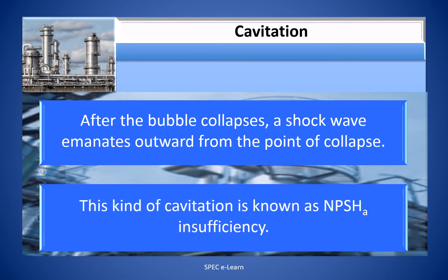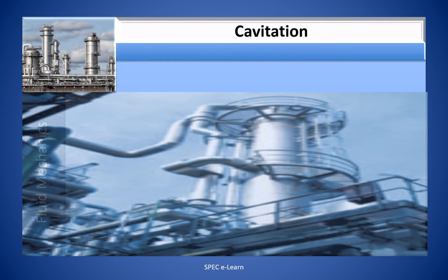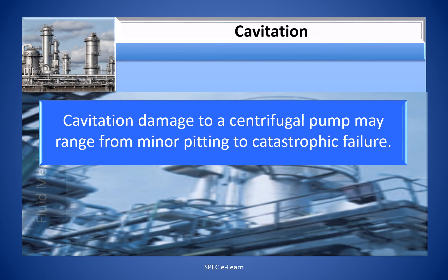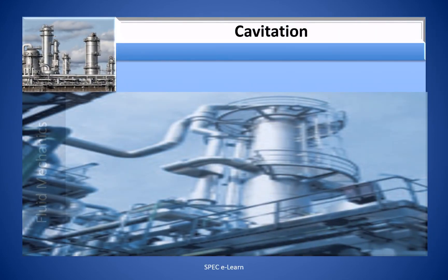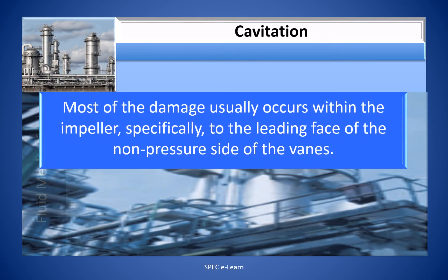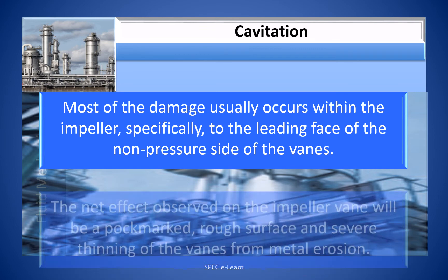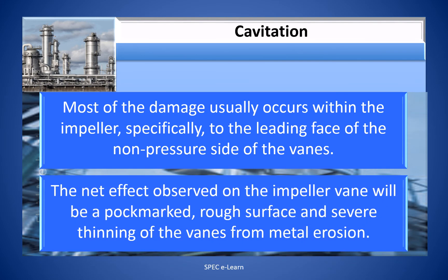Cavitation damage to a centrifugal pump may range from minor pitting to catastrophic failure. The damage depends on the pumped fluid characteristics, energy levels, and duration of the cavitation. Most of the damage usually occurs within the impeller, specifically to the leading face of the non-pressure side of the vanes. The net effect observed on the impeller vane will be a pockmarked, rough surface and severe thinning of the vanes from metal erosion.